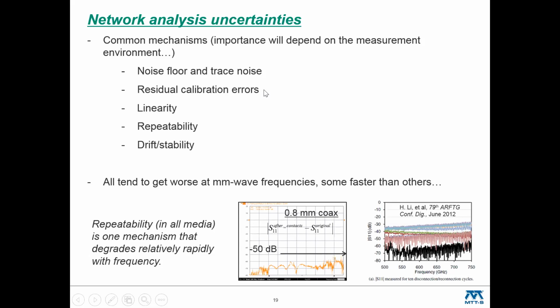Residual calibration errors, how well do you know your standards, is really what that boils down to. And that isn't getting worse very dramatically either. Linearity, we mentioned, is getting worse in absolute terms, but not so much in net terms, and I'll show a curve in a minute to explore that a little more. What does get worse a little more rapidly are things in the area of repeatability and drift.